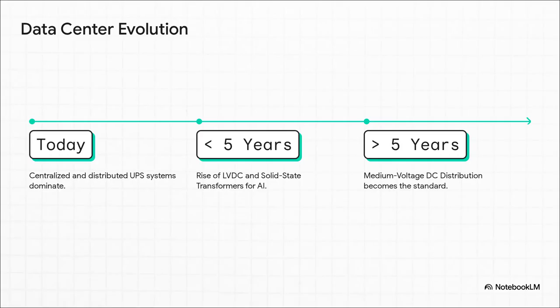As you can see from this timeline, data center design is an incredibly fast-moving target. The transition from traditional UPS systems to direct current distribution and solid-state transformers isn't happening over decades. No way. It's happening over a span of less than 5 to 10 years.